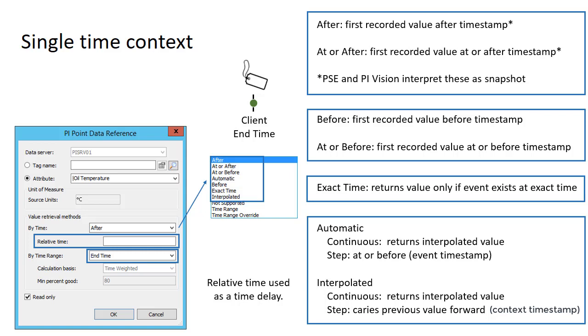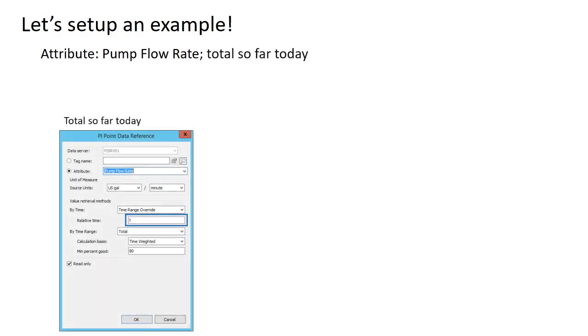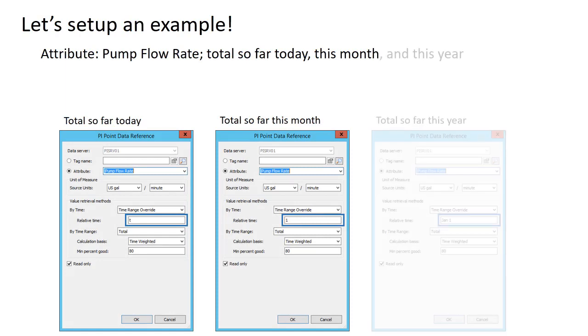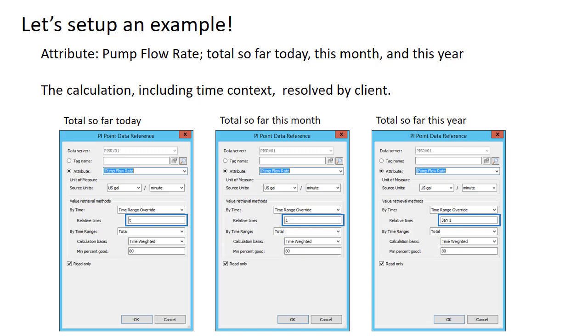Let's set up a simple example. We have an attribute for the pump flow rate in gallons per minute. We would like three more attributes that show the total flow so far today, this month, and this year. In each case, the relative time is set to determine the time range over which we would like to take this total. The calculation is resolved locally by the client and is not saved in a PI tag. This means that PI time like T, or midnight associated with today, is the local time of your client — so different people on different machines in different time zones will have different midnights resolving for this calculation.